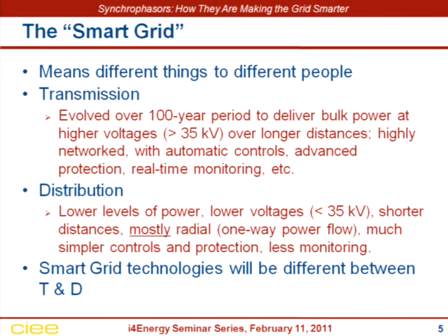One thing you learn when you dig into this is that smart grid means different things to different people. It also means different things whether you're talking about transmission or distribution. For those not familiar with the differentiation of the electric system: transmission has evolved over a 100-year period to deliver bulk power, high amounts of power, usually from remote large power plants at higher voltages, usually 60 kV and up, that's 60,000 volts and up. It's highly networked, highly meshed, with a lot of automatic controls, advanced protection systems, and real-time monitoring and control, and a lot of other great attributes. Distribution is usually at lower levels of power and voltage, usually under 30 kV or so. Power goes shorter distances, and it's mostly a one-way flow from the transmission system through a step-down bank to the distribution.